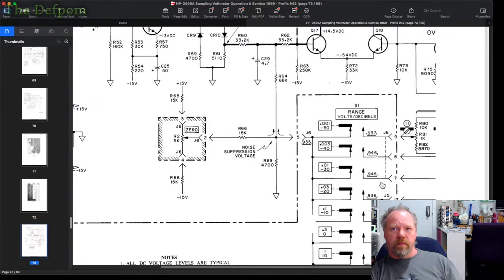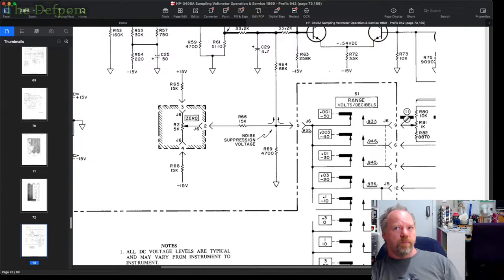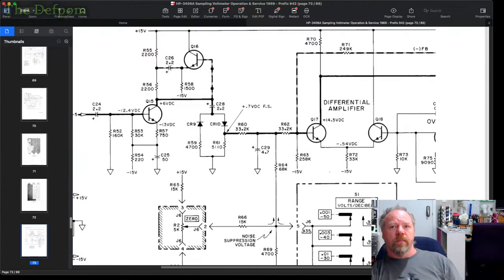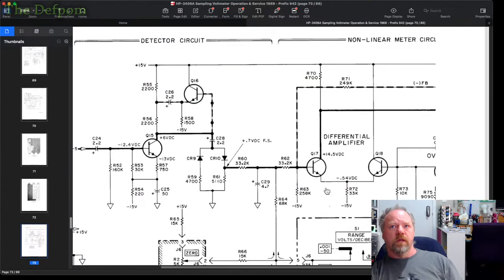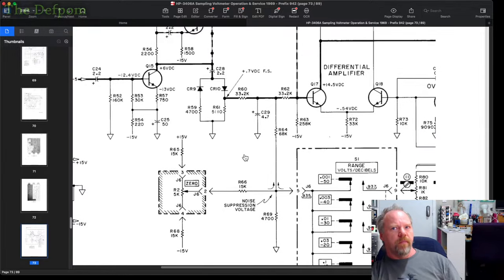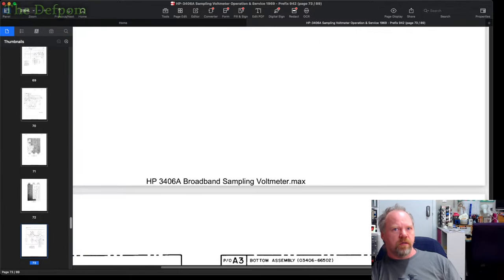Again, this is part of the switch matrix. Maybe there's a problem with switches. I did do some checking. I couldn't find any problems. Switches appear to be working correctly. So it's got a non-linear meter circuit section here, which allows for a skewing of the amplification ratio as the signal levels come up. So it's got a built-in compensation to level it back out again. But yeah, I haven't done any testing really on this side apart from the zeroing and a switch.